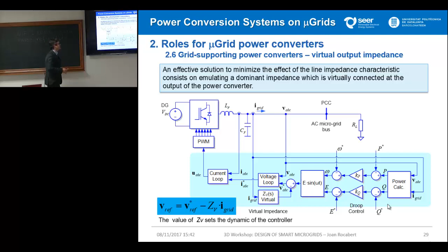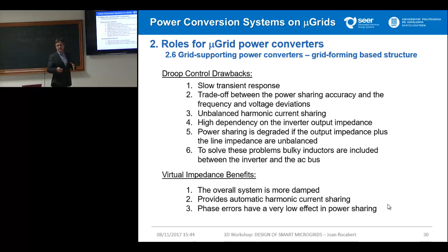So the virtual impedance gets some benefits over some of the drawbacks of the droop control, and these benefits are related to the overall system. It's more damped, this virtual impedance. It's able to provide automatic harmonic current sharing, something that the droop equation is not able to do, and the phase error has a very low effect in the power sharing, because now we have decoupled the P and Q droops from the real line impedance.